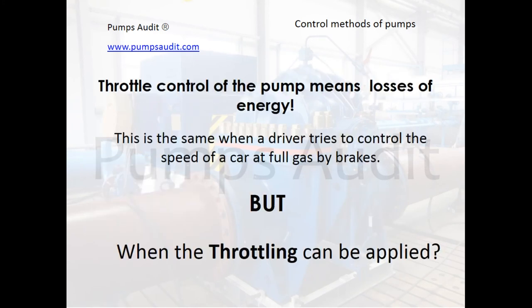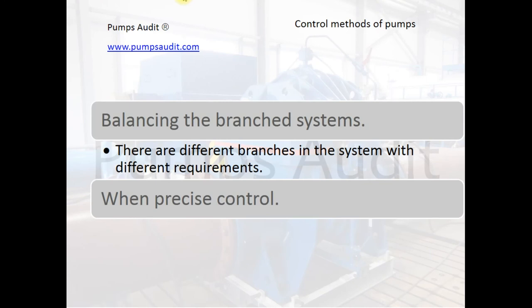Sometimes throttling can be the only solution for rescuing a pump and an electric motor. It is clear that throttle control means energy losses — it is the same as a driver trying to control the speed of a car at full throttle using the brakes. However, throttling can help pump users avoid more serious problems. There may be other situations where throttling can be applied, for example for balancing branch systems when there are different branches with different requirements, or when precise control is necessary.